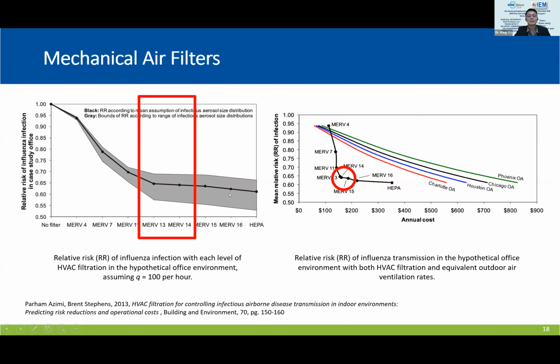They are quite equivalent, because using HEPA and MERV 13 results in a huge pressure loss through the filters, which ends up having a drawback on the energy consumption of the system. So most experts recommend MERV 13 or 14 would be good enough, while HEPA is optional, or more of a luxury, so to speak.